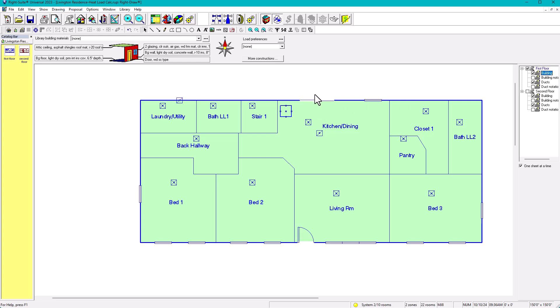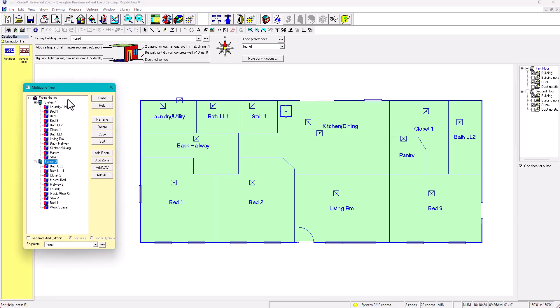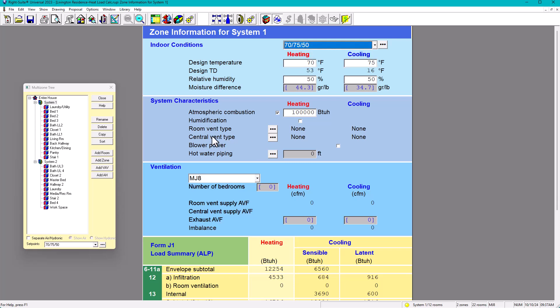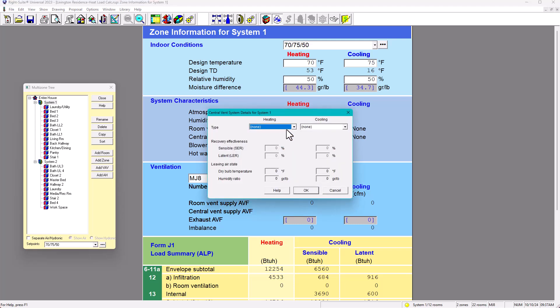The third step is to make sure your settings are correct. You have to use the multi-zone tree because it lets you specify which system you're configuring — System 1 or System 2. Go to System 1, click on it, and then go to Zone Information to verify all settings. For System 1: indoor conditions are 70°F heating, 75°F cooling, and 50% relative humidity.